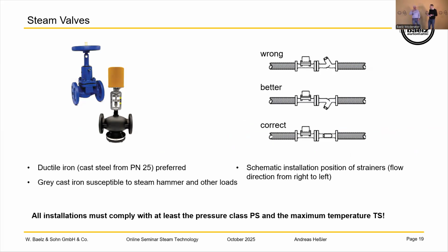Yeah, that's what I said before. When you don't put it sideways, you put it down like the better version, and you have steam inside, the steam will condensate and fall down to the lowest point of the strainer. Then maybe you close the pipe, and in 2 days or so you have water inside and open the steam really quickly, and then you get hammering, and the strainer can break. When you put it sideways, like the correct version, no condensate can stay there, so the condensate can fall down to the next steam trap, so you have no hammering and no destruction of the strainer.